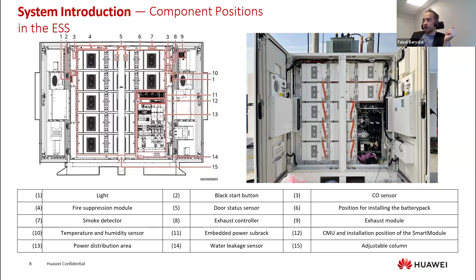When it comes to the installation, it's important to keep in mind some small details, especially how you have to install the PCU and also the fire extinguisher unit, which just goes on top of it. It's important that you make the right measurements, so the fire extinguisher should be a reliable source — when there is a fire or smoke inside the battery, it should be able to operate. That's why during installation and supervision, when we are on site, we make sure that this fire system works and functions as it should before we start up the system.